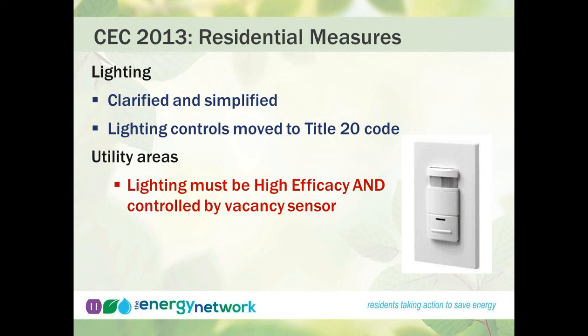One of the big changes that is, I think, a rather big issue is that the lighting must be high efficacy, such as fluorescent or LED, and have a vacancy sensor control in the utility area. So where you have a closet or utility space, typically we could have an occupancy sensor or a fluorescent light, but now we need to do both. We need to have both a high efficiency light and a sensor so that it turns off when they're not present in those spaces.